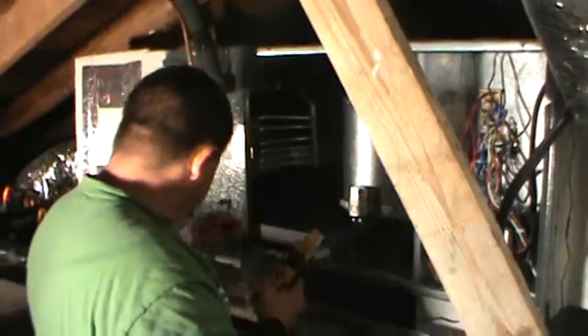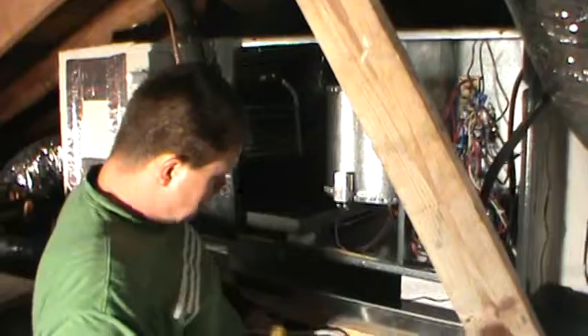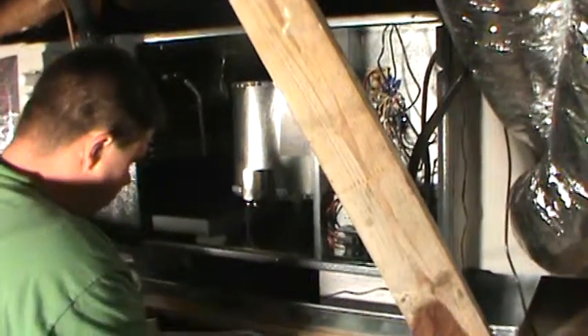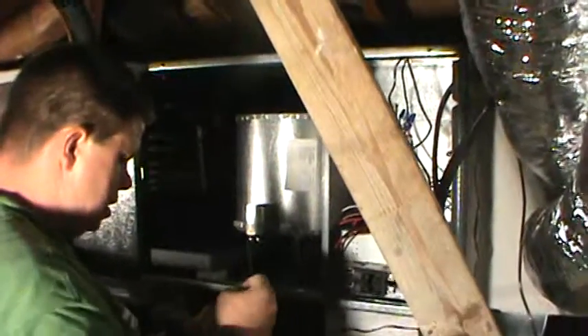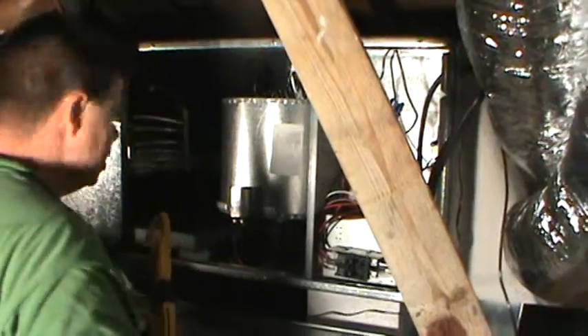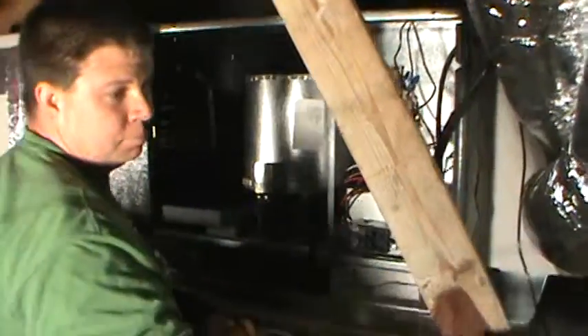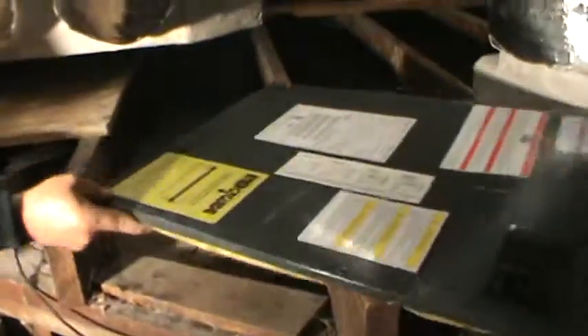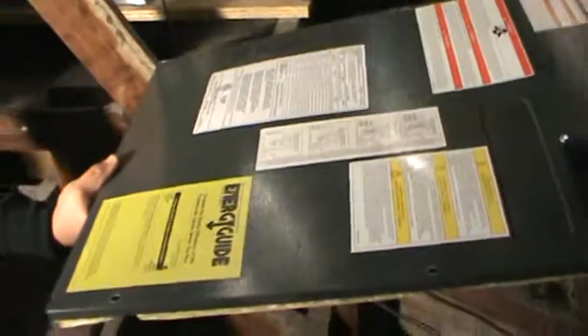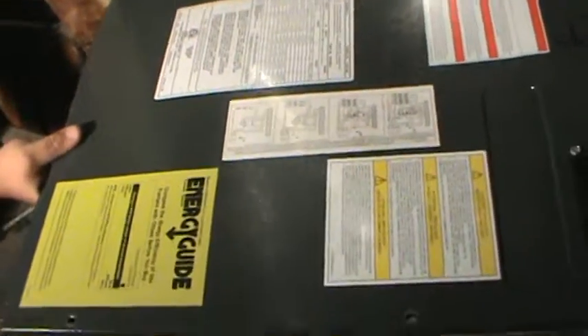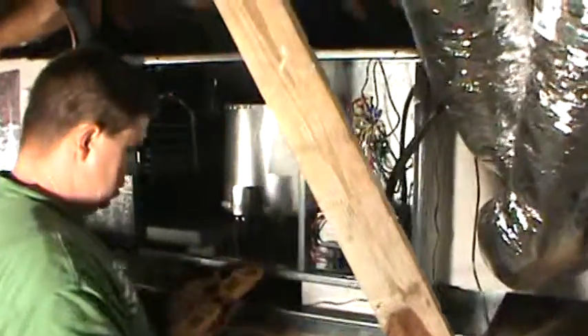That's all good. Now I set the thermostat down there for the fan to come on. So when we put power back to it, just the fan will turn on. You want to check the amperage of this motor. You want to check your panel to see what the manufacturer calls for, and on this motor it calls for 2.64 amps as its normal running load.